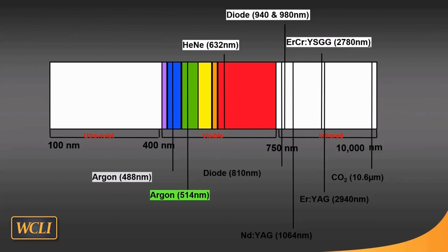They're soft tissue lasers. And then as we move on into the red, most of the lasers, actually all of the lasers that we use in dentistry, are invisible to the human eye. So all of them come with something called an aiming beam. And sometimes the aiming beam is green and sometimes the aiming beam is red. But this shows us that, number one, the fiber is intact. It shows us that our tips are intact. It shows us that everything is working the way it's supposed to. And in some cases, it will actually even show us exactly where we're cutting or where we're about to ablate if we have to hold our tip a little bit further away from the tissue.